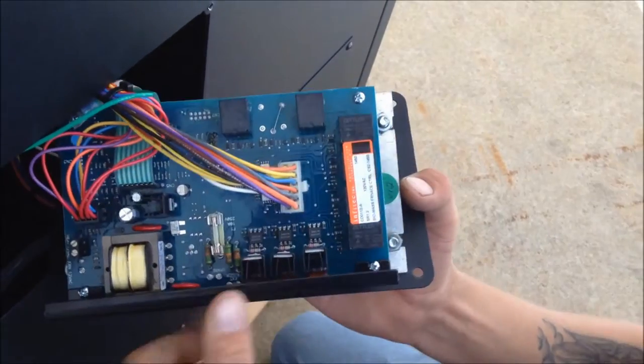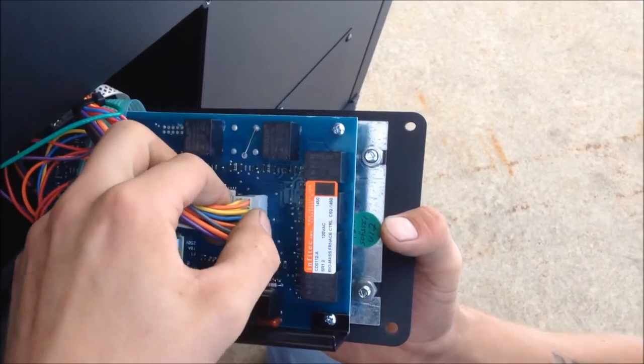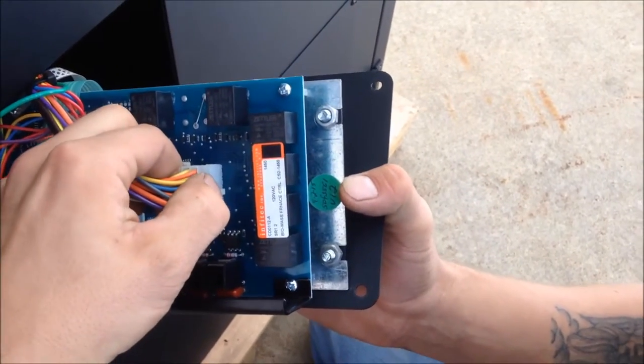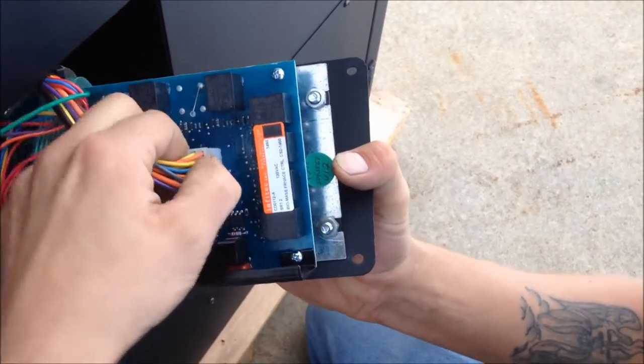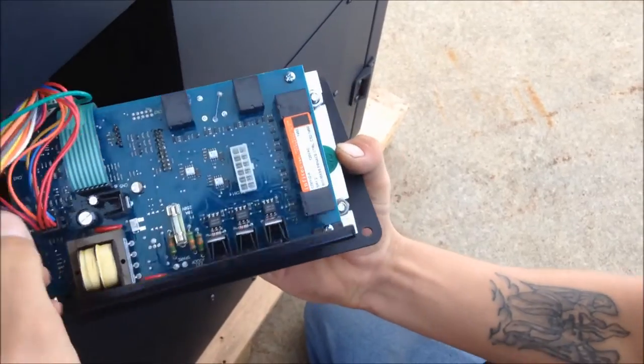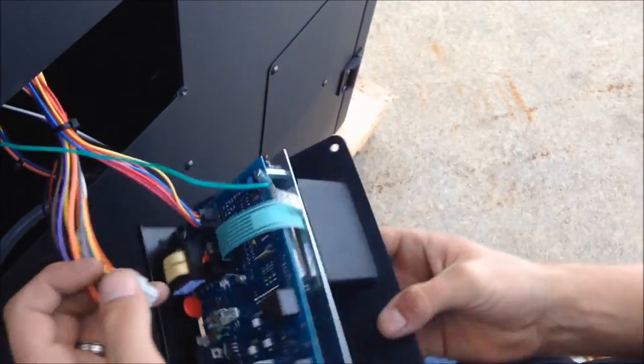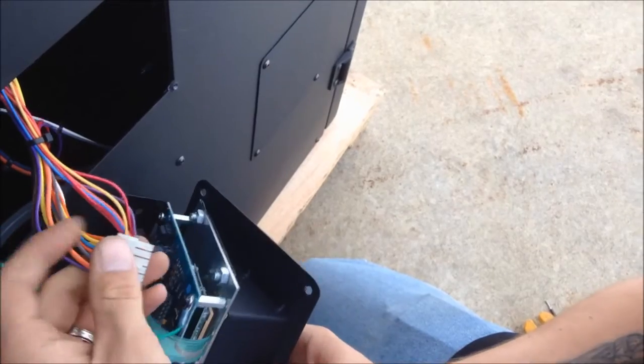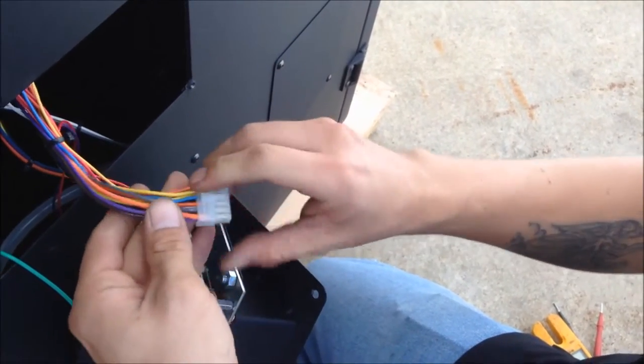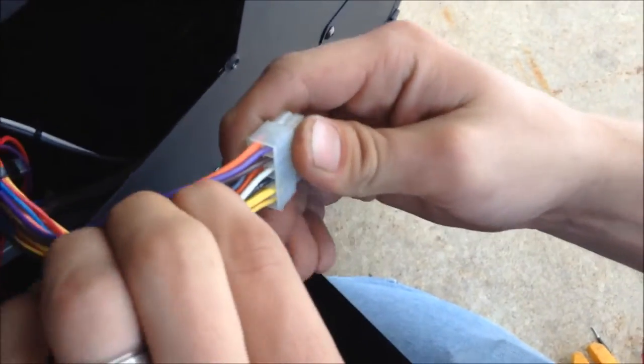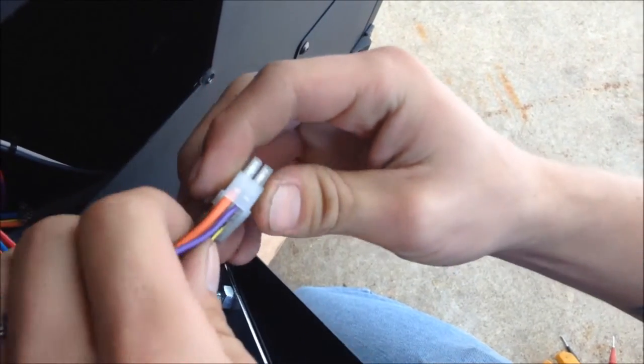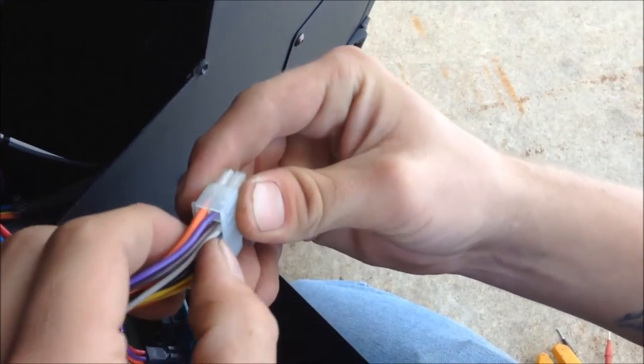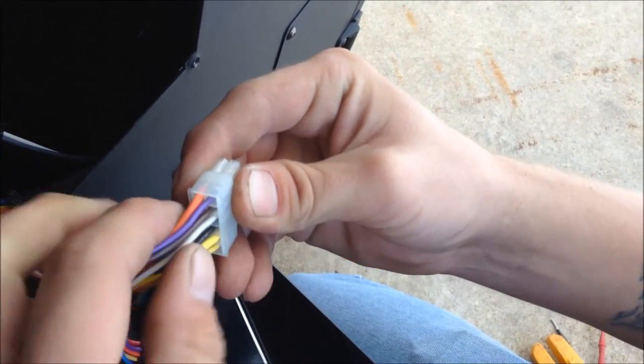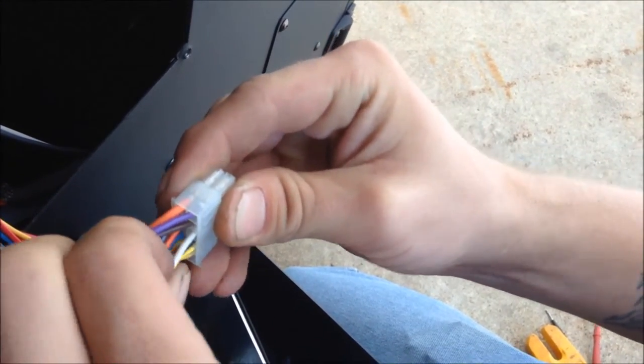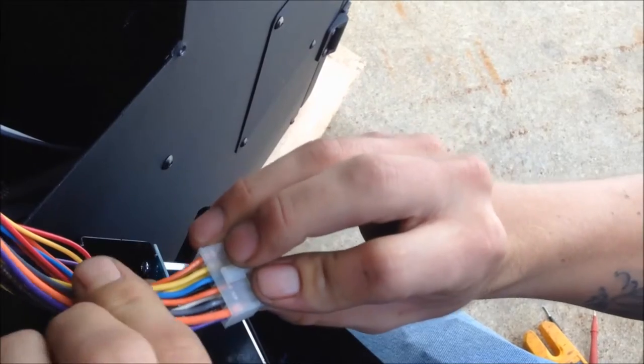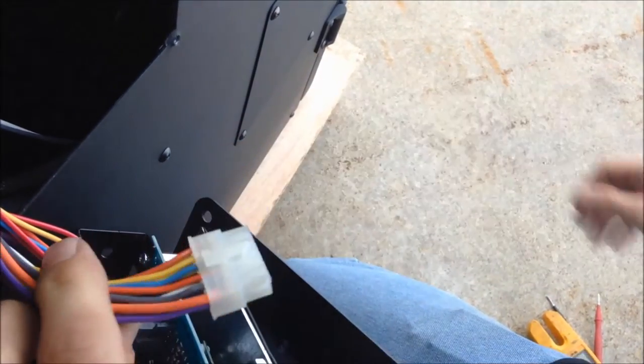Next, we're going to troubleshoot the wire harness. So if you grab this white clip right here, depress the hook. Carefully position your control board so you don't scratch the panel. And we're going to be checking the back of the wire connections. If you see a metal prong sticking out of the back of the white clip, it's not getting a good connection. And we are okay on this one.